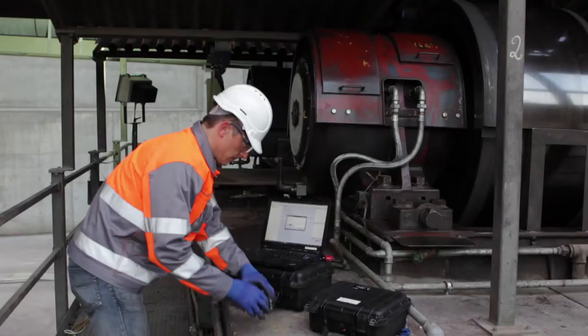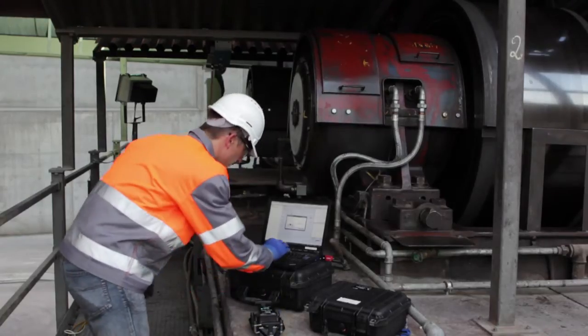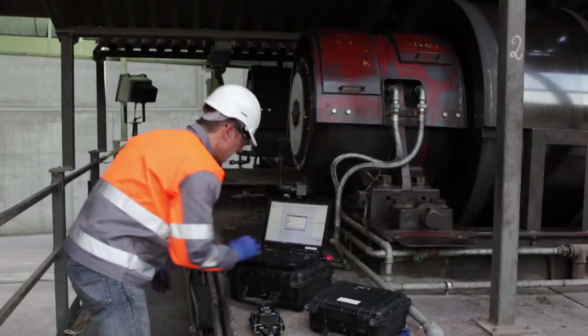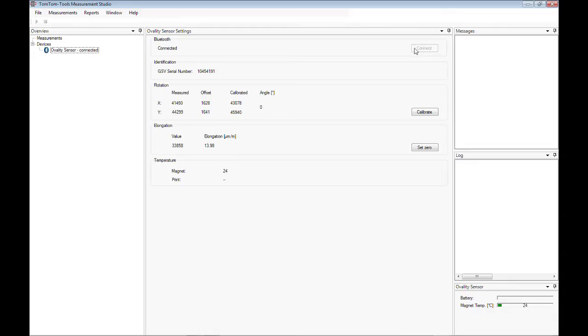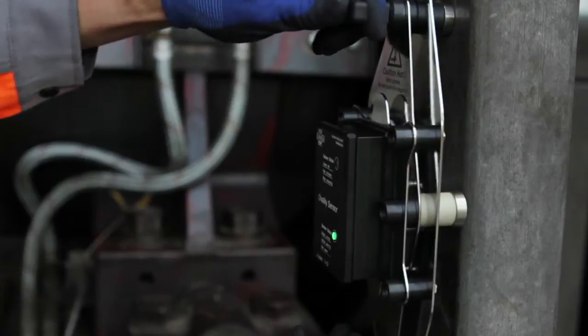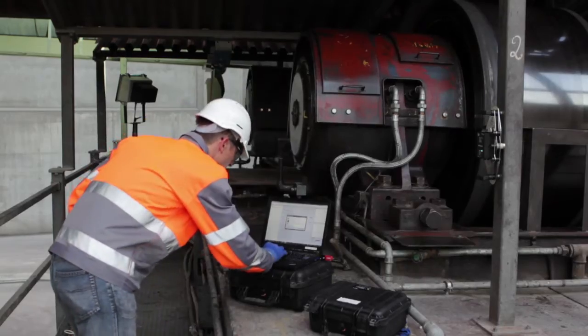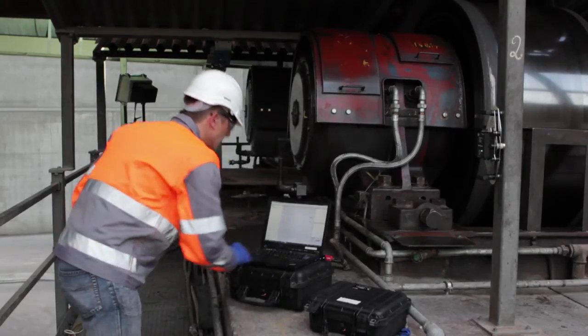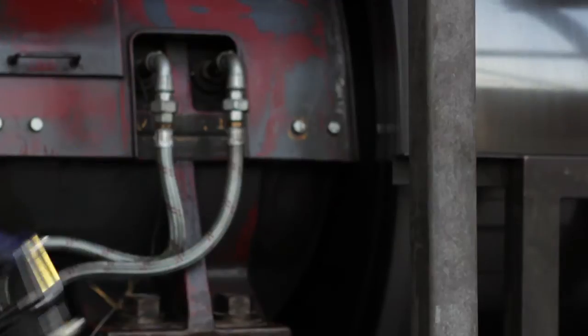Once the ovality sensor is connected to the laptop, the orientation sensor can be calibrated. After placing the tool on a horizontal surface, push the button calibrate in the software. Then click next and hold the sensor onto a vertical surface. Push the next button one more time and the calibration is done.